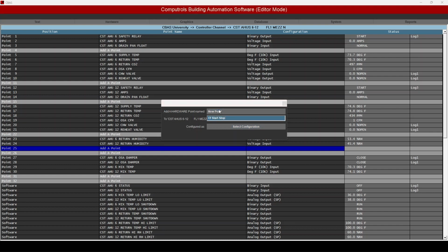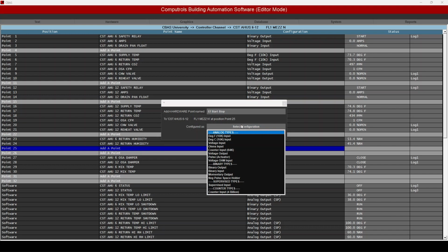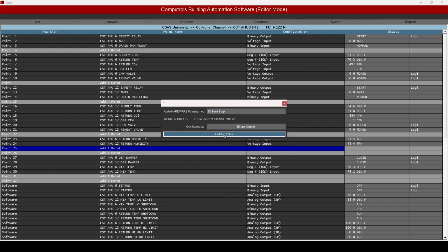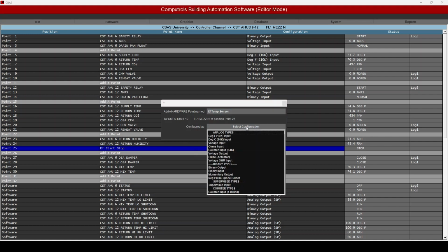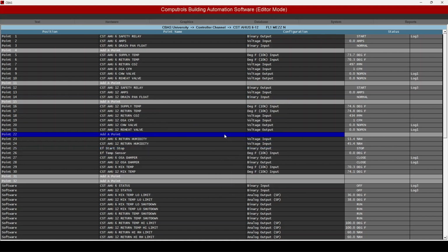I click on any open point in the system and simply say I want this to be a relay — so that's a binary output, start, stop. Next I want to add the temp sensor. The system remembers I'm working with the EF, so I can just add on to that. There's my temp sensor, which is a degree Fahrenheit input, automatically scaled for a 10K type 3.